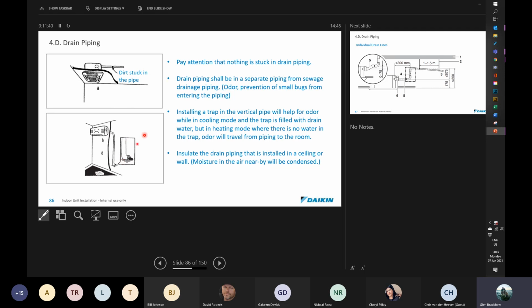Okay. Also, drain piping should be separate from sewage piping, okay, to prevent odor from going back into the building, and also all the other things that grow inside sewage pipes. Installing a trap in the vertical line will help for odor. In cooling mode, the trap is filled with drain water, but in heating, when there's no water in the trap, the odor will travel up the pipe, and this often happens in the winter months. We start getting some bad smells coming back through the aircon units because the P-traps have dried out.